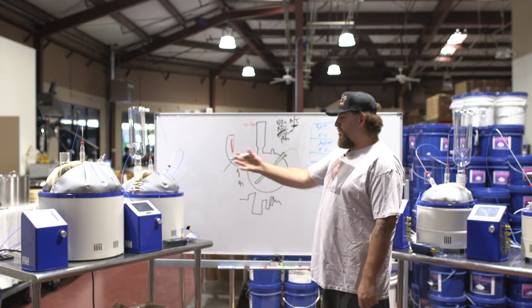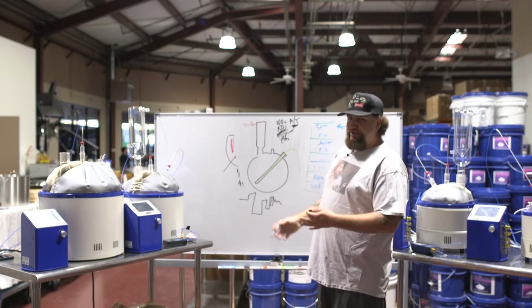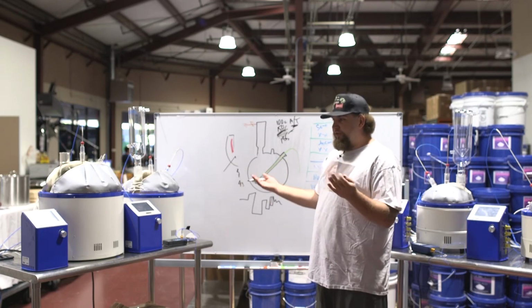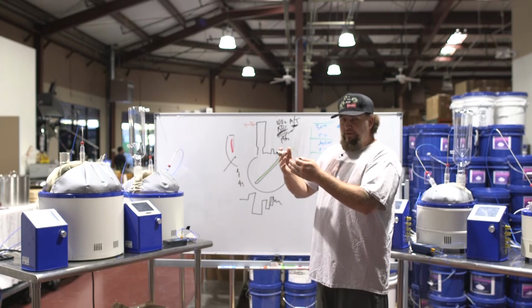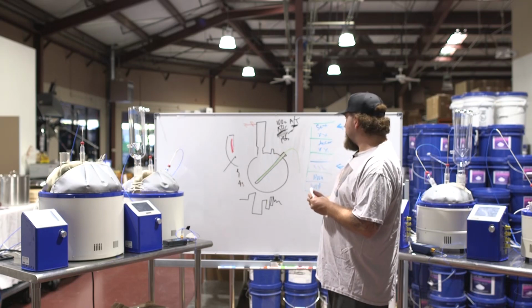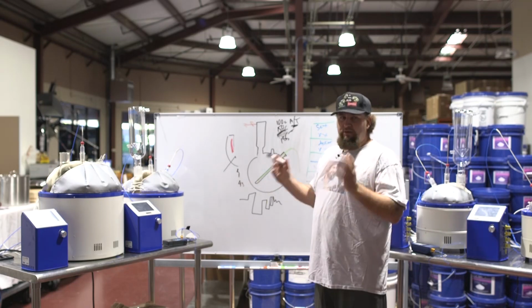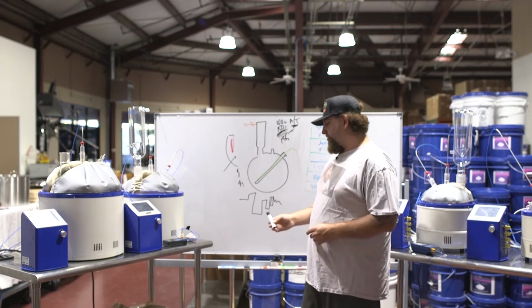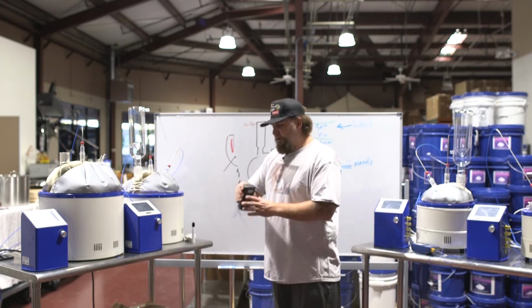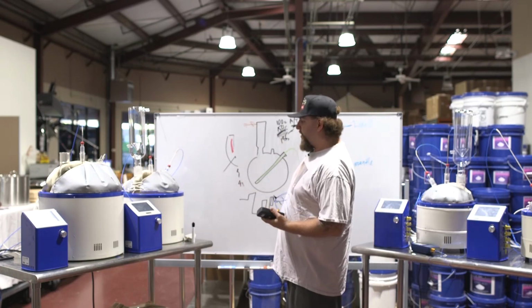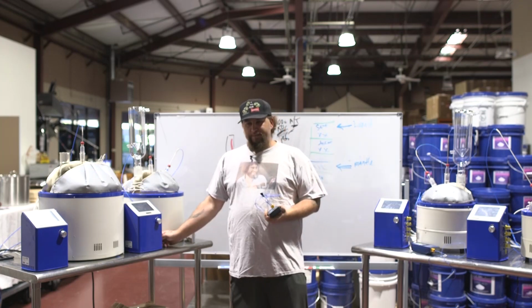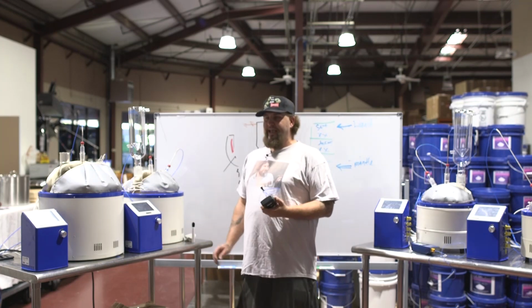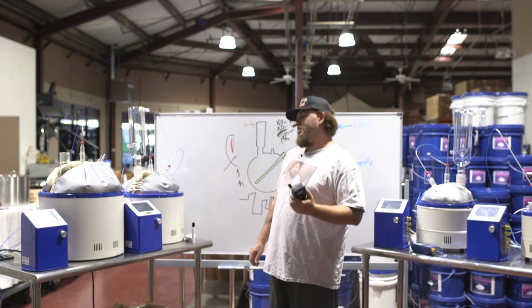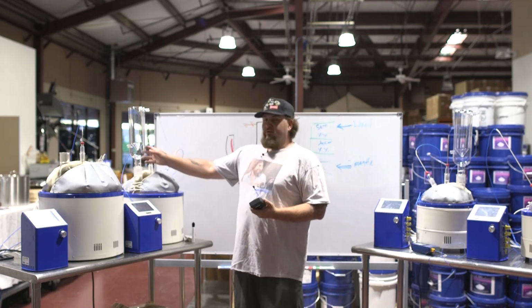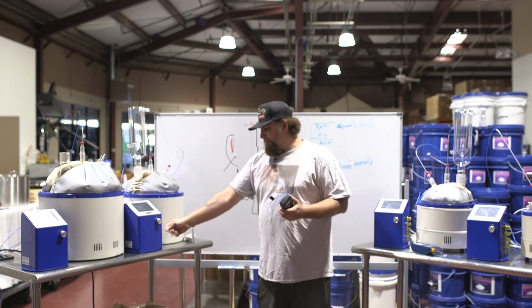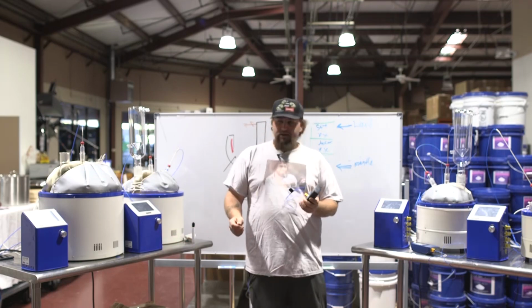So what happens is I'll just go up to 185. Now I've gone to temperature and I see, oh, everything's within a degree, but everything's there, it meets up. So I go to 185, and then all of a sudden I'm at 185. So the next procedure is as follows. You take your thermometer, and then you plug in your vapor probe. So you're gonna calibrate everything to this number. That means I'll remove the trap, and I'll take my vapor probe, and I'll just sit it in there.